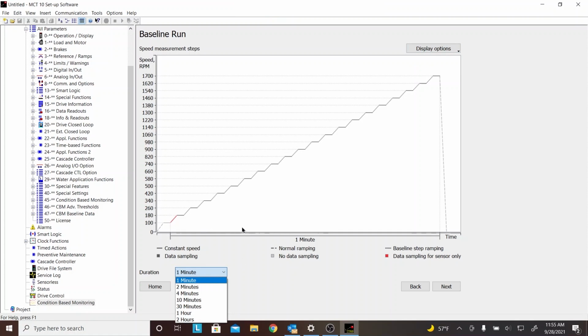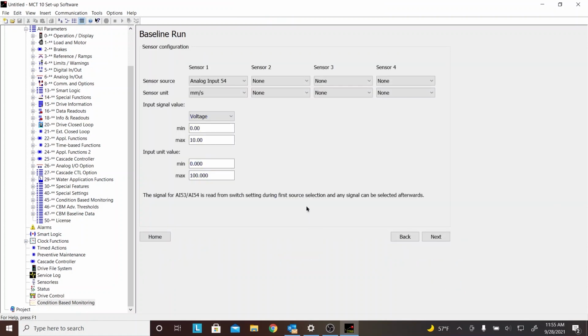So what this means is if I choose 1 minute, that means when I hit the go button to gather this information, it's going to run from 0 to 1700 RPM in 1 minute and gather all this data. All these points of data are going to be registered in 1 minute. Now I could choose 30 minutes, an hour, 2 hours, whatever. If you had the ability to do that, let's say it's a fan, you could do it. It might be an easy and quick way for you to set this up. So once you're in there, you hit next. Again, logical order, it wants the next step.